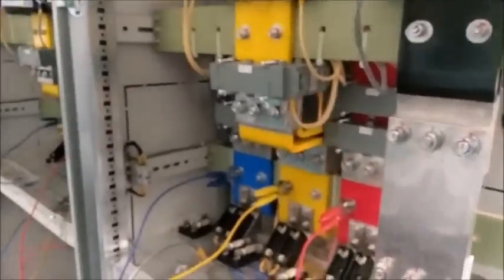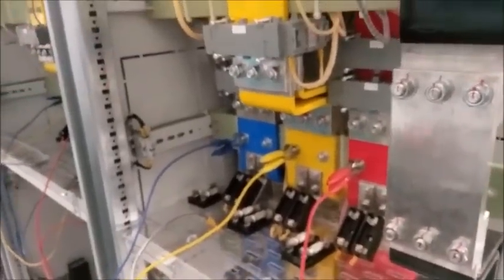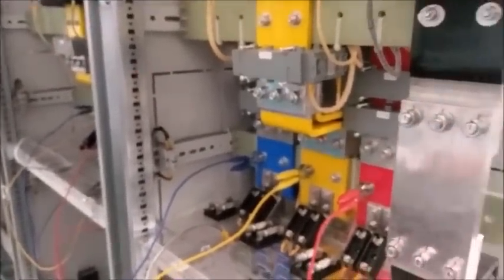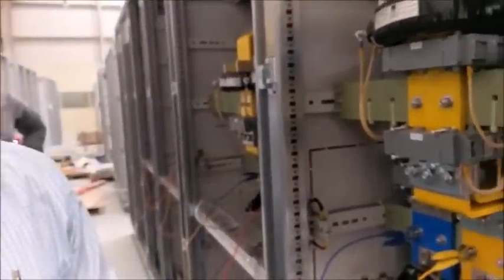Now see, what we have done is tested this complete panel from here to there for the HV test. This is a completely automatic test, meaning we are not doing anything. We apply the voltage as per the standard for 1 minute and it should pass this test. And then you will do the Megger again, the same way that we did earlier.